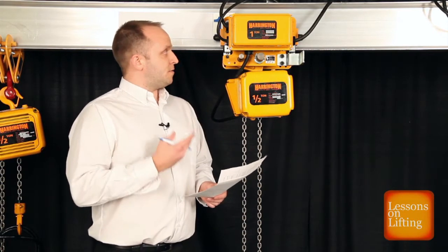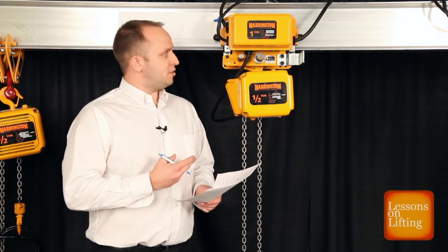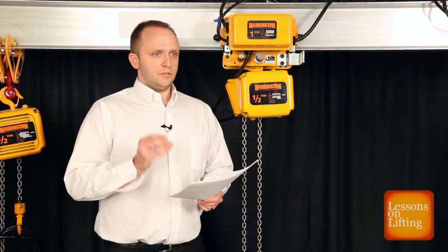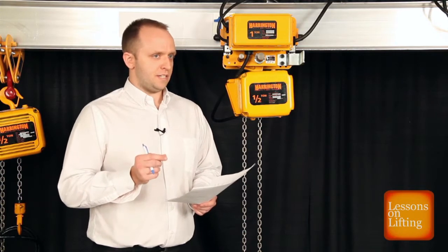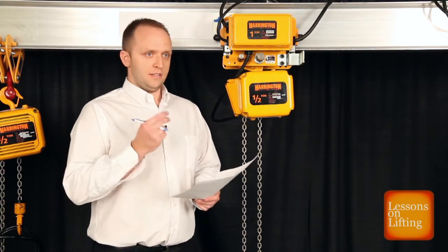We can perform voltage changes on single-speed units. That's an important thing to note. Dual-speed units, that is not possible due to the voltage-specific VFD inside either the trolley, the hoist, or both.